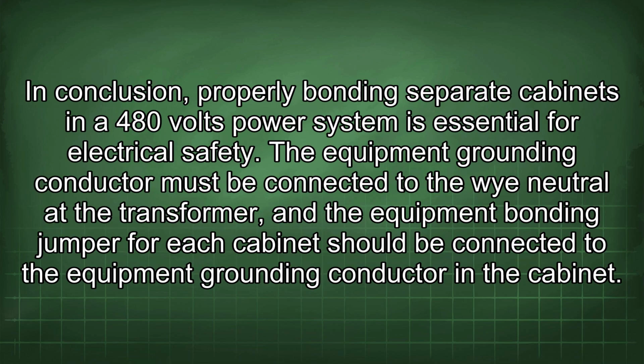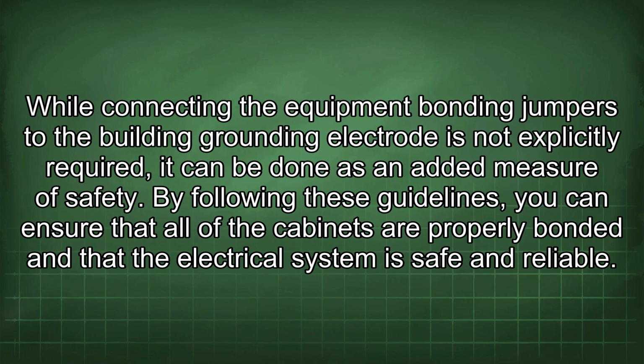In conclusion, properly bonding separate cabinets in a 480 volts power system is essential for electrical safety. The equipment grounding conductor must be connected to the wye neutral at the transformer, and the equipment bonding jumper for each cabinet should be connected to the equipment grounding conductor in the cabinet. While connecting the equipment bonding jumpers to the building grounding electrode is not explicitly required, it can be done as an added measure of safety. By following these guidelines, you can ensure that all of the cabinets are properly bonded and that the electrical system is safe and reliable.